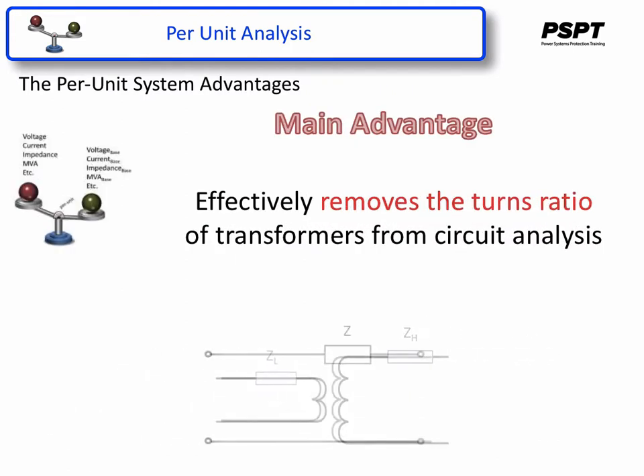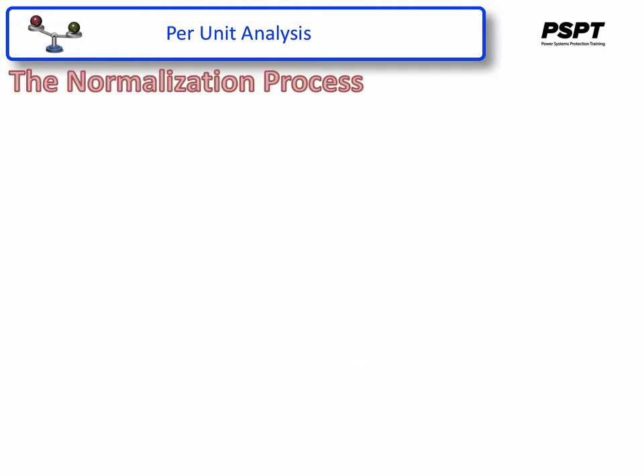The main advantage of the per unit system is it effectively removes the turns ratio of the transformers in the systems being analyzed. The normalization process has five steps — some people refer to them as rules. There are four steps going into the per unit system and then one step that takes you back out into the regular system.